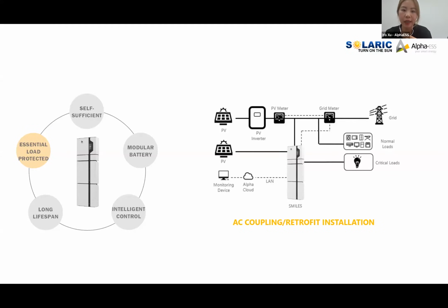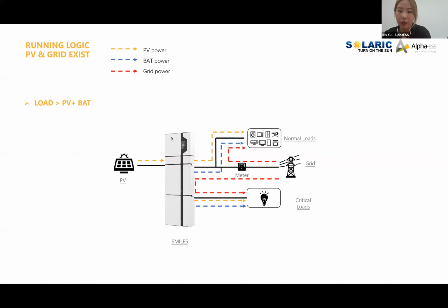Now let's look at the running logic. As mentioned, the system's main feature is to maximize PV generation. We want to use PV generation as the first priority to power all our loads. If PV is not enough, the battery will kick in to help PV power the load. But if that's still not sufficient, the grid can also help. So if the load is larger than PV plus battery, all power sources — PV, battery, and grid — work together to power the load.